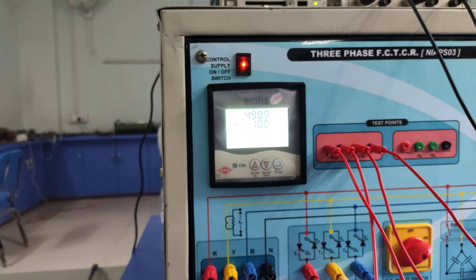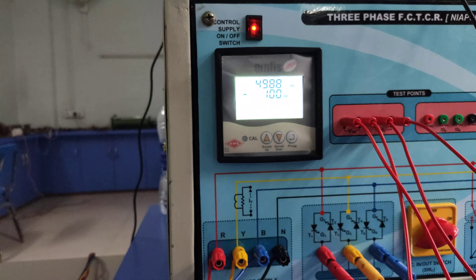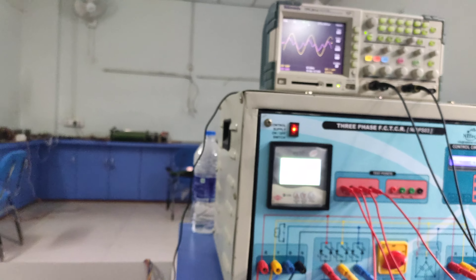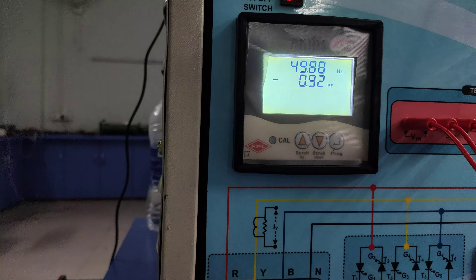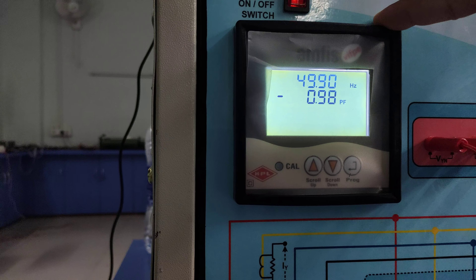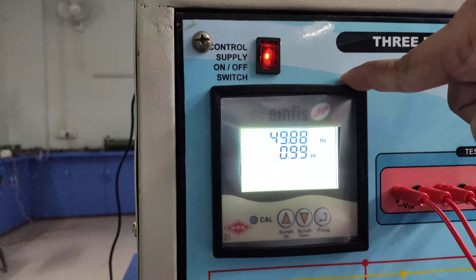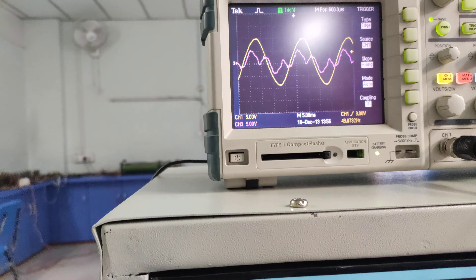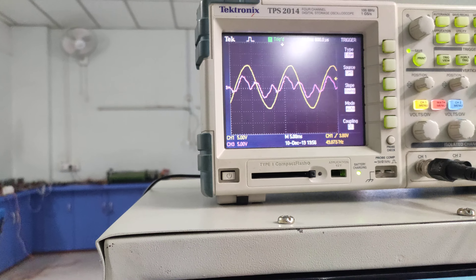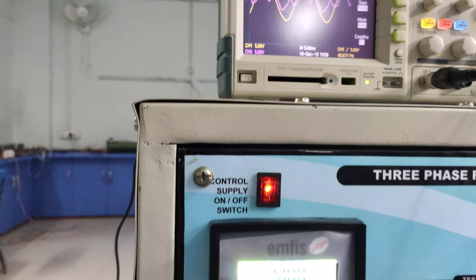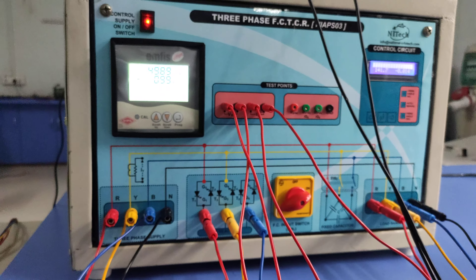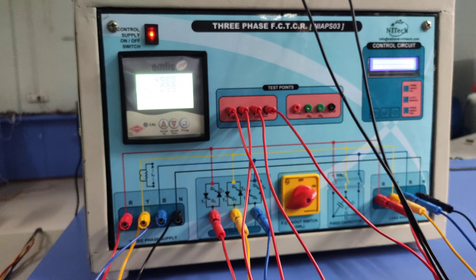So this is a closed loop action — the controller will directly adjust the firing angle to make the power factor unity. I also turn off my second load bank. Again the power factor is poor and the controller will take action to make the power factor unity by changing the firing angle. So this is the closed loop mode of the FCTCR kit.